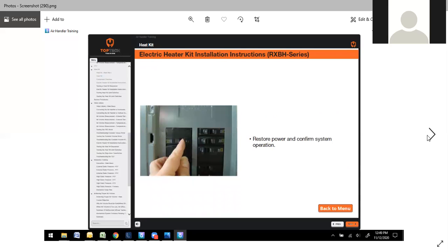Once you're done, restore the power back on. Now, what I would tell you, if you're installing a heat pump air handler, obviously check your heat pump, make sure it's working okay. But as a byproduct, you also want to, number one, check your emergency heat, the heat elements by themselves. What I would do is put my meter on there. I'm checking amp draw on however many elements I've got. I want to watch, number one, that they're engaging, and then I want to make sure that each element kicks on. Then I want to make sure each element kicks off.